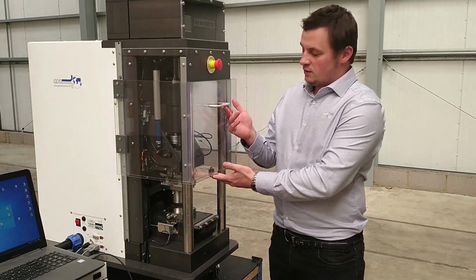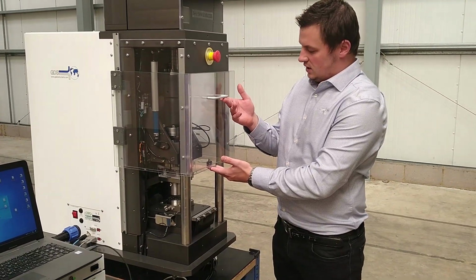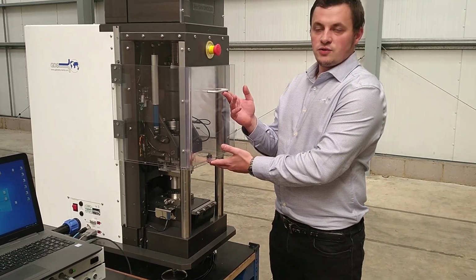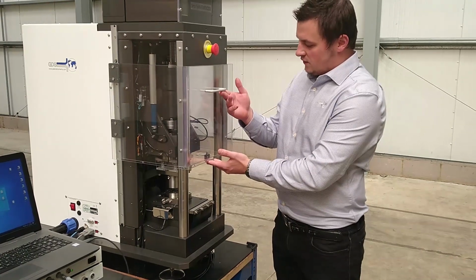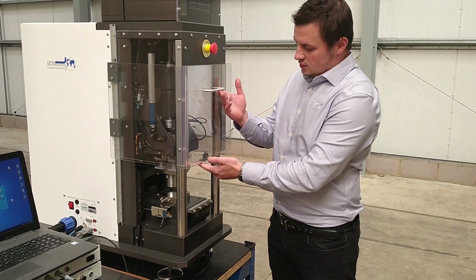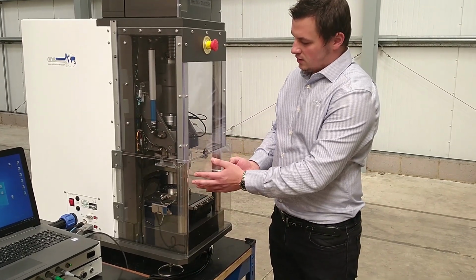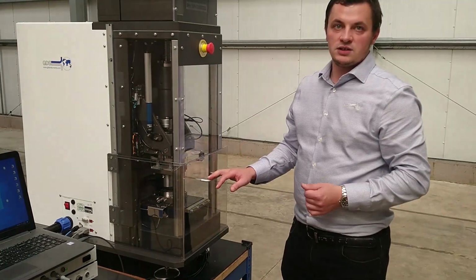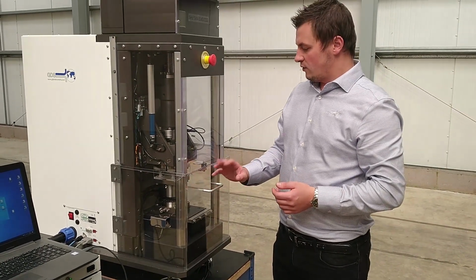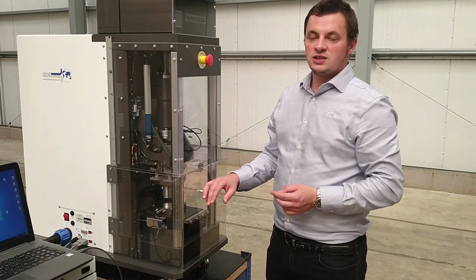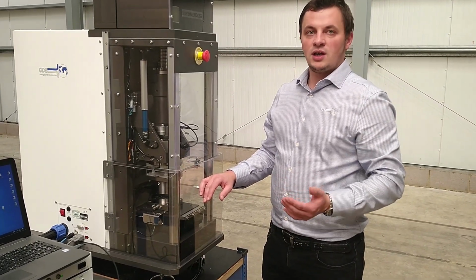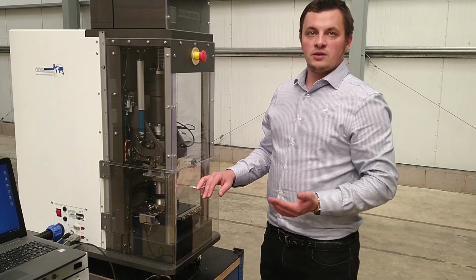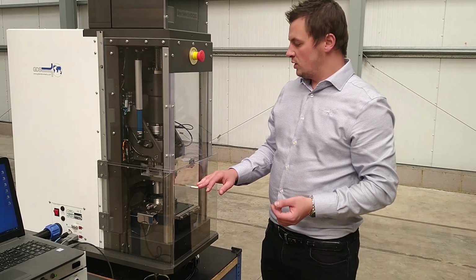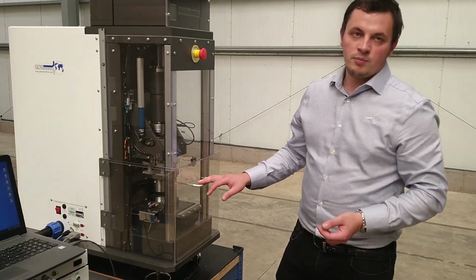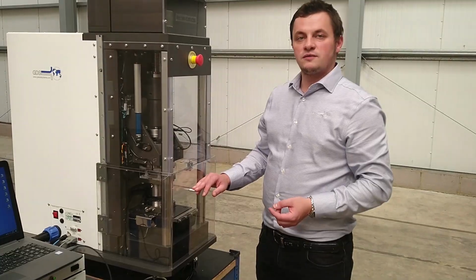Please remember that during the actual test, if the temperature control in the laboratory is not very good, ensure that the cover is placed down, which will protect the transducers from any sudden temperature changes, like the AC units kicking in or someone opening up the door or opening up the window in the laboratory. Will ensure better stability of the results and of the transducers.